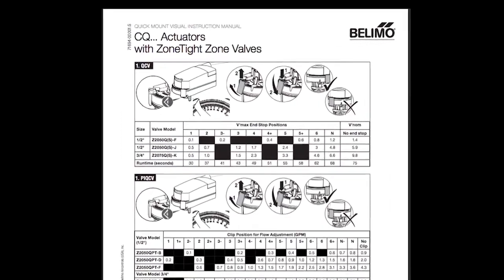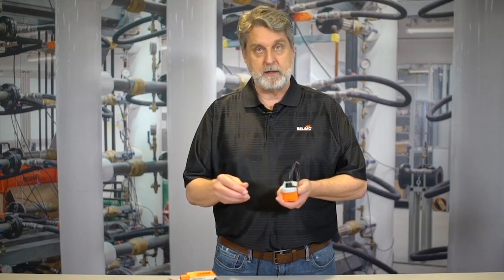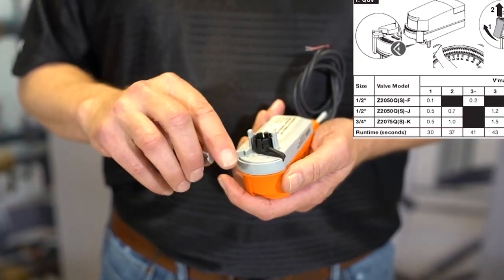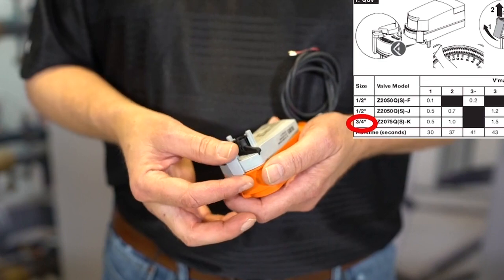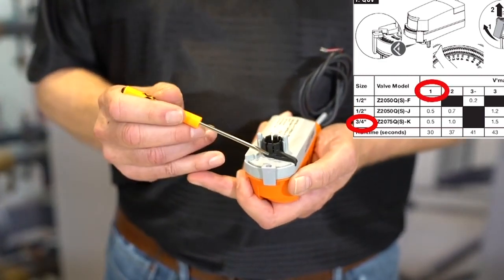It's going to give you flow in CV. So, if I'm putting this on a VAV box and it calls for a half a gallon per minute flow, I look at the table. It tells me, because this is going to be on a three-quarter inch valve, I need number one for the clip setting. Very easily, I clip it on.